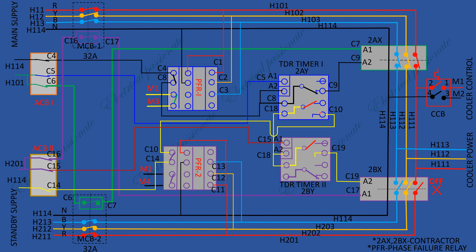Now suppose main power supply through MCB1 fails or a single phasing occurs. This contact will break the circuit and no power returns through this circuit. Therefore, the 2AX contactor breaks the circuit and this contact will make to give access of neutral to the 2BX contactor through timer 2 after reset time. Now cooler power is on standby supply.